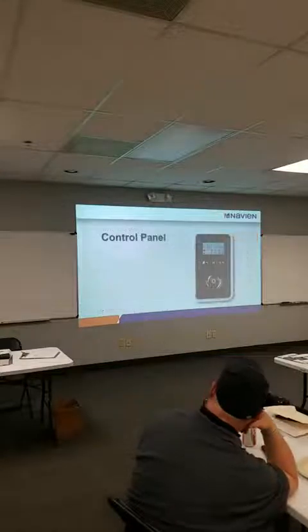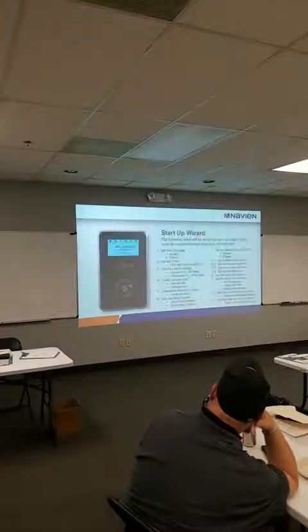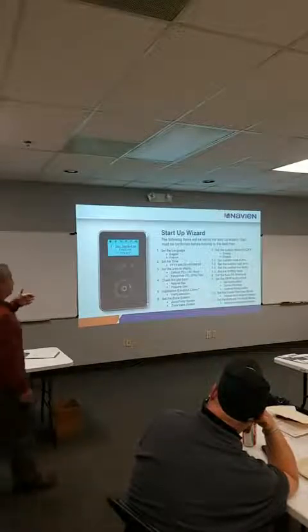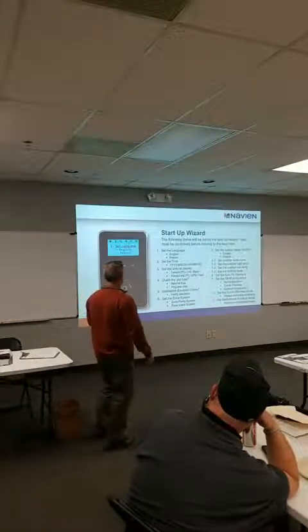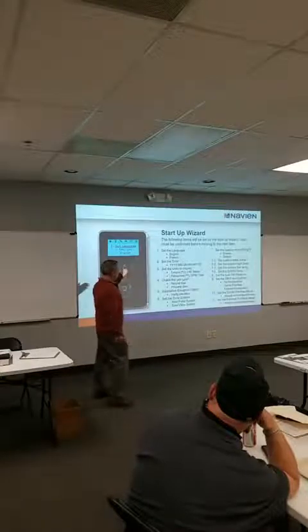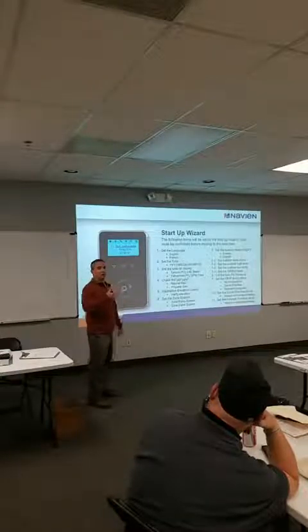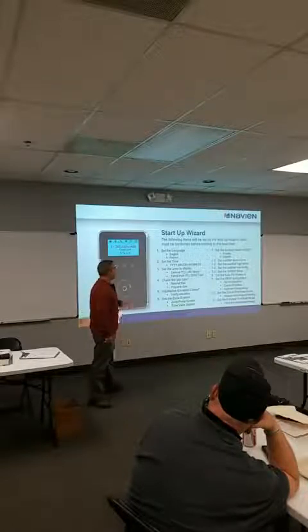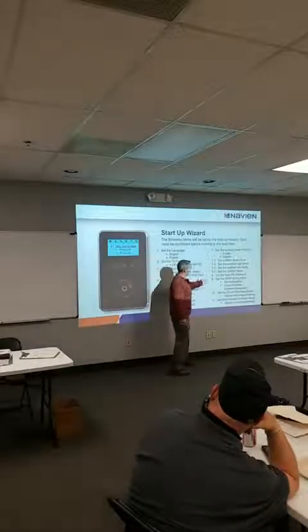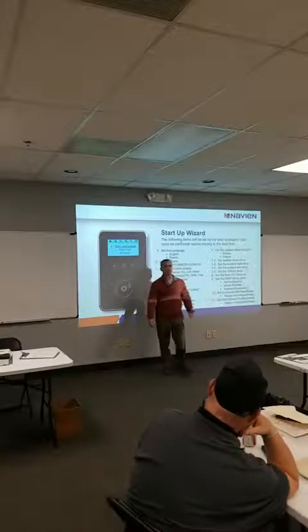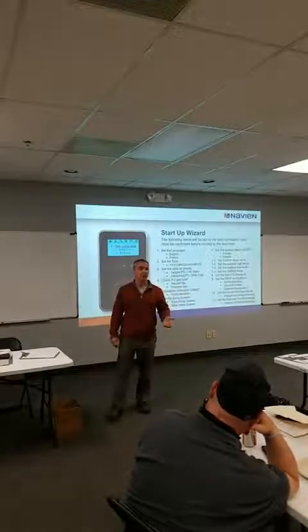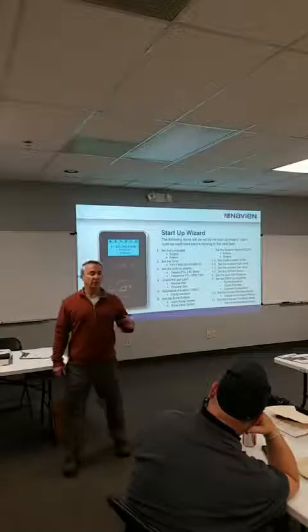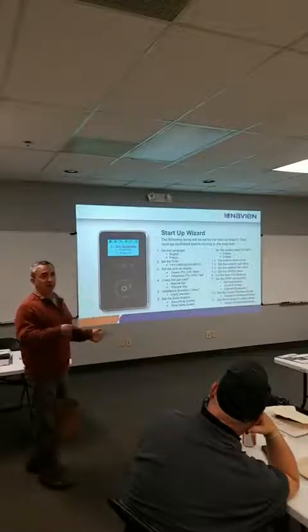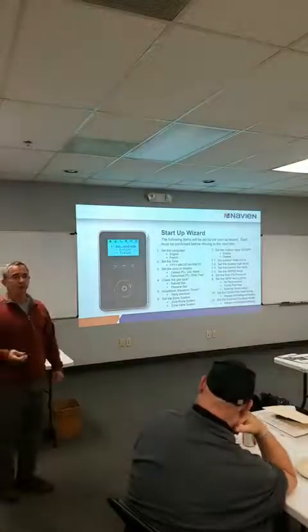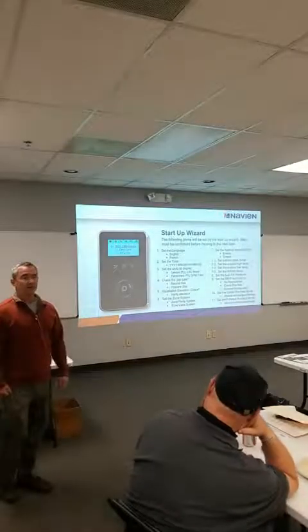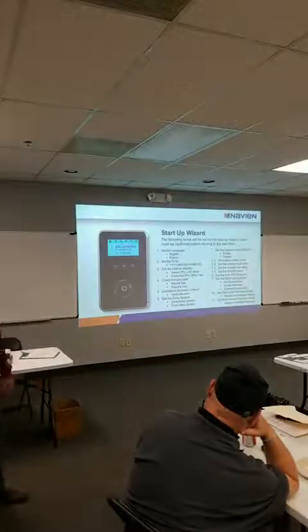So here's the keypad. We already talked about everything on here. This is the startup wizard that's going to be on all the equipment. On the combi or on the boilers, it forces you to go in and check all your settings to make sure you set it up properly. On the combi, it's going to ask you recirc questions. Are you doing domestic recirc? How do you want to run it? So regardless of who you send out, for the most part, they should be able to do a quick start programming and get the system up and running. If something's not running right, you can go back and adjust the system.